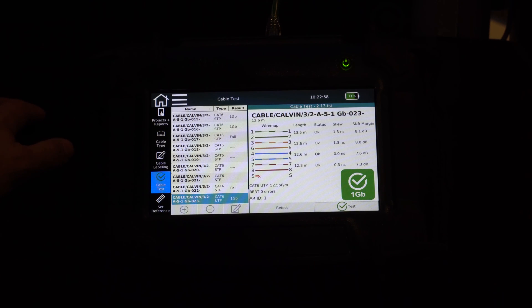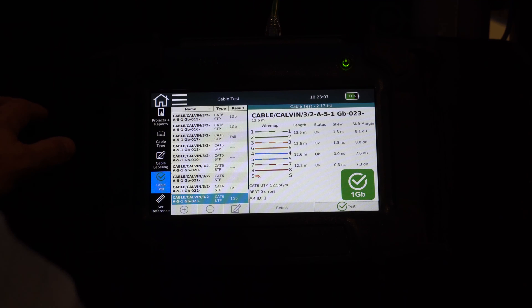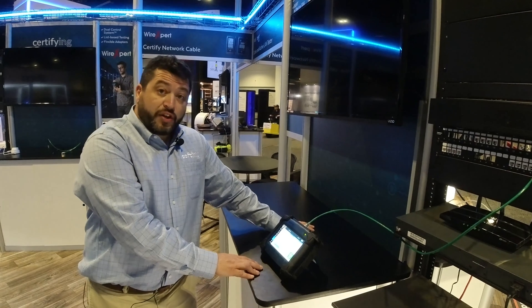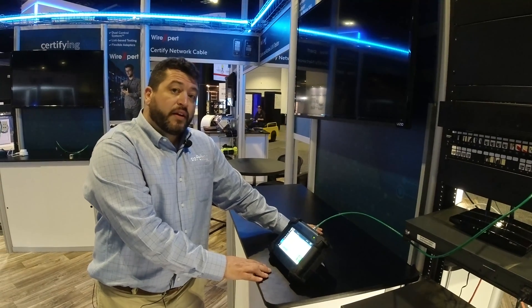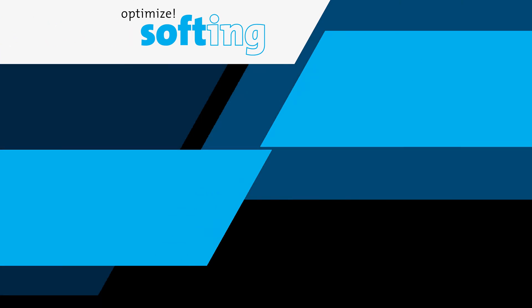You can see the results here — all four pairs are wired correctly, there is no shield. You get the length of each pair, the skew of each pair, and the signal-to-noise ratio of each pair. We ran a BERT test and there were zero errors. It's a good cable, ready to support that camera at the end of this cable run.